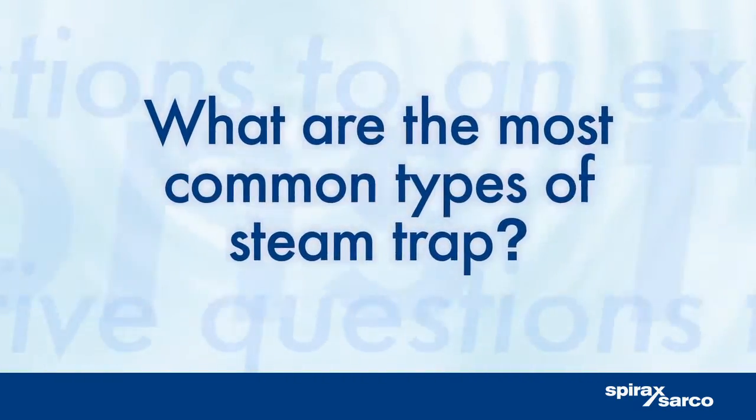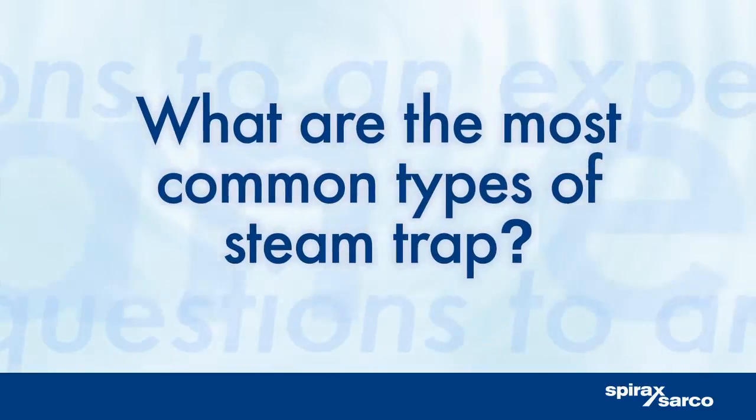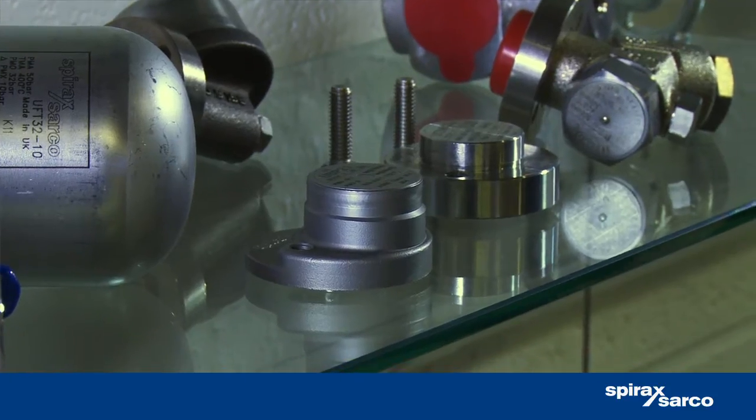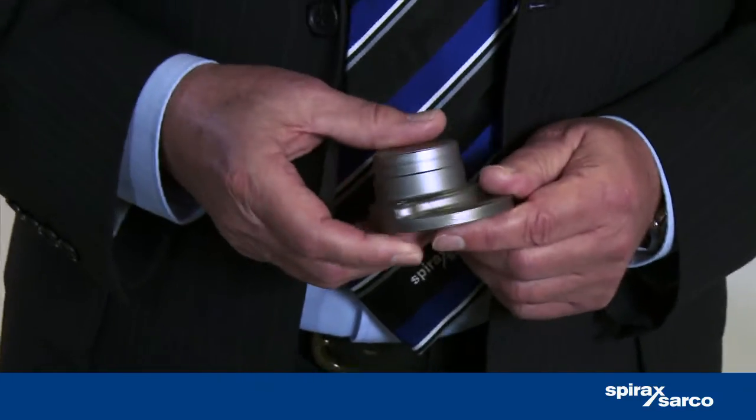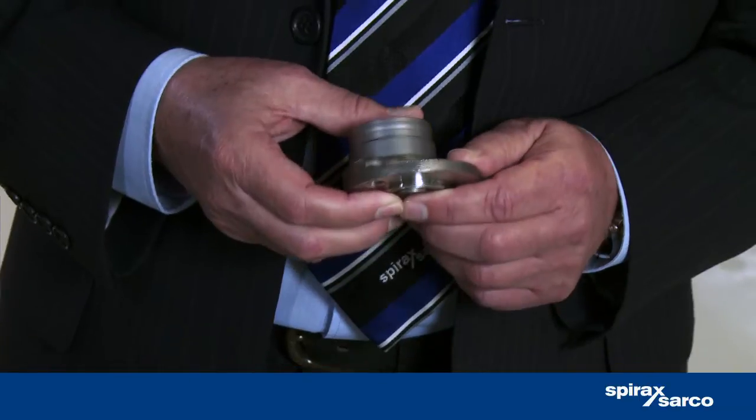Getting the right steam trap for the application ensures the highest productivity and energy efficiency. What are the most common types of trap? Thermostatic steam traps operate by using the temperature difference between steam and condensate. These traps are great for applications such as trace heating and small steam heating packages.